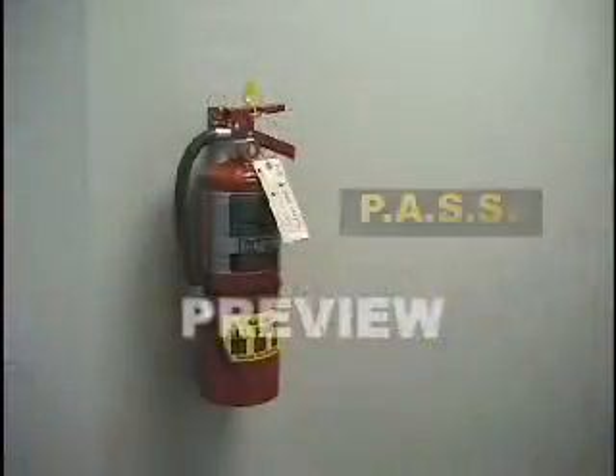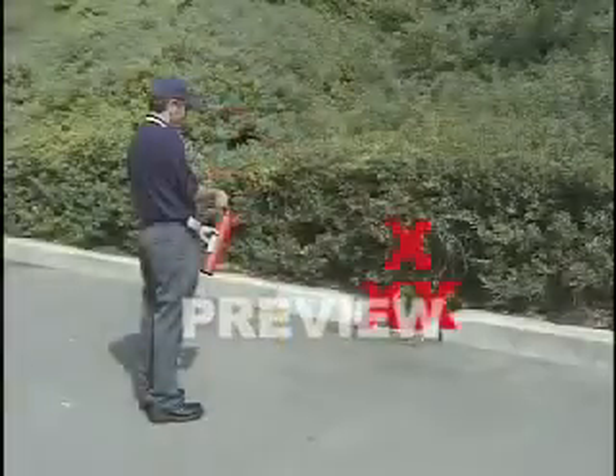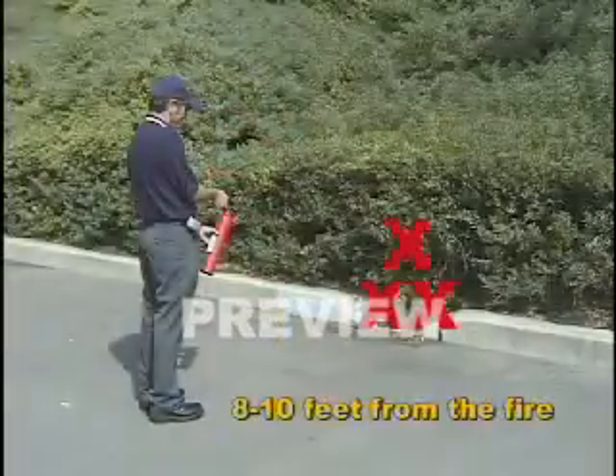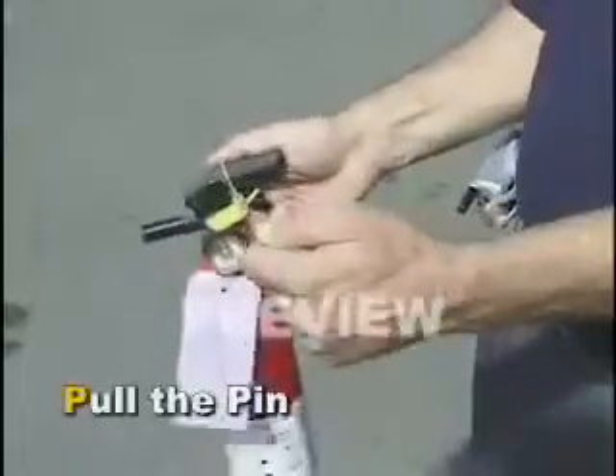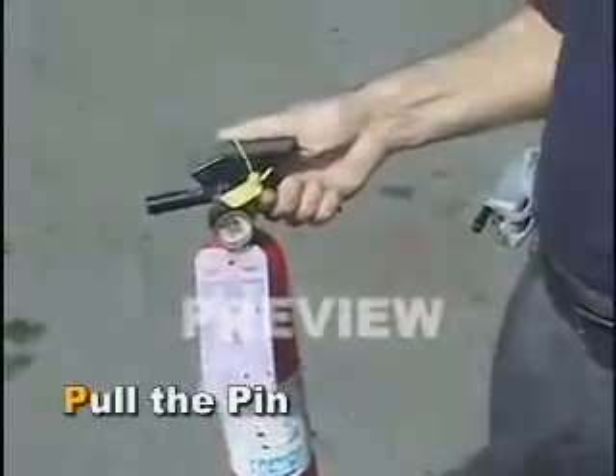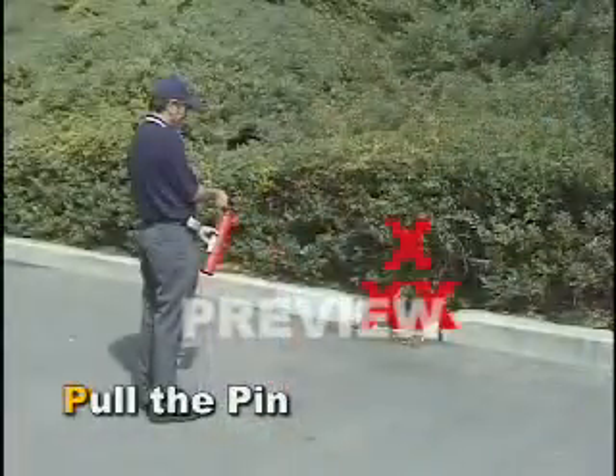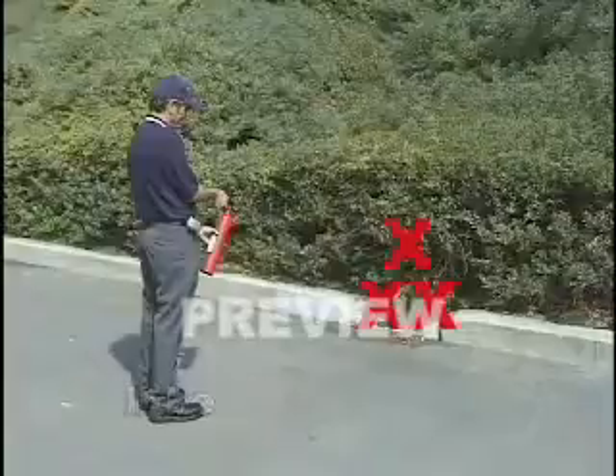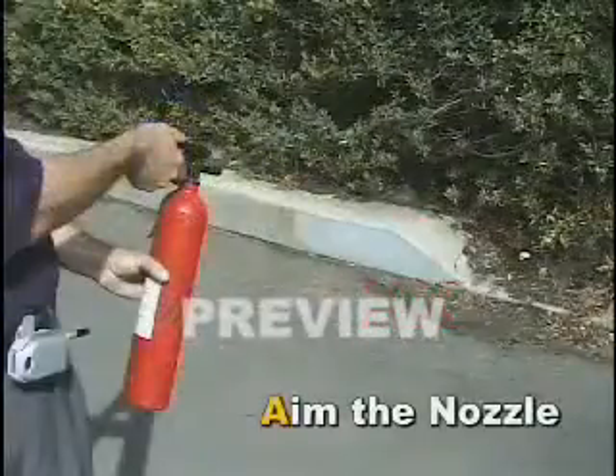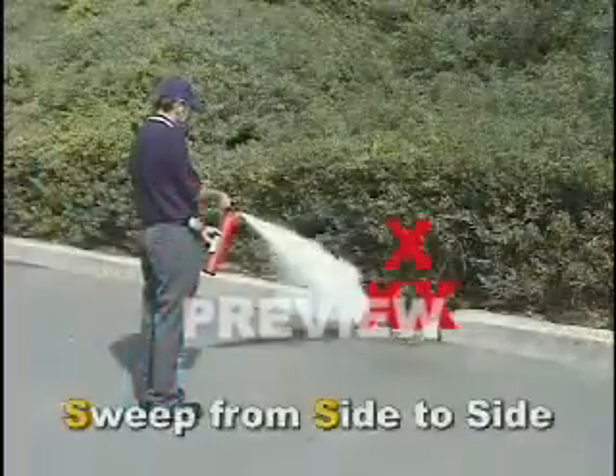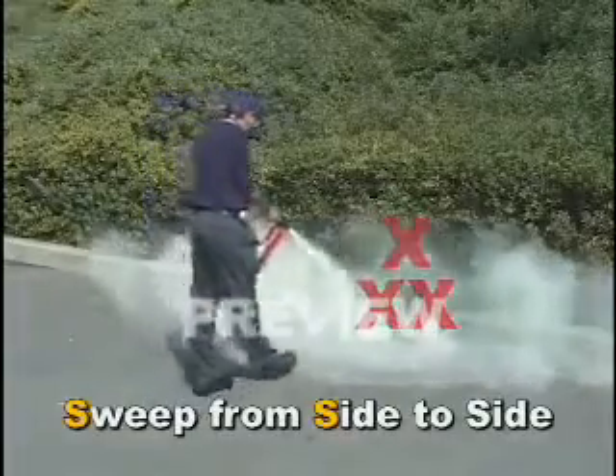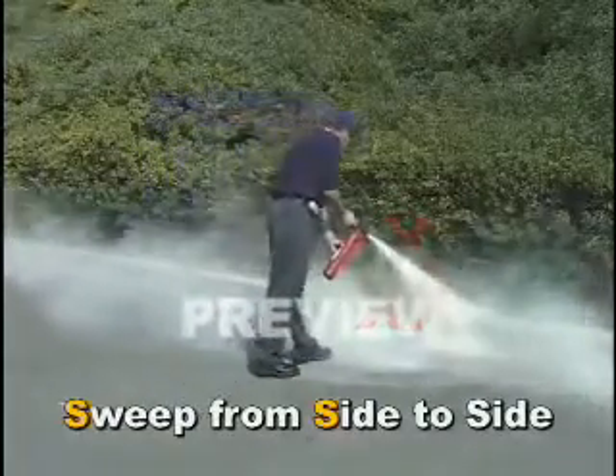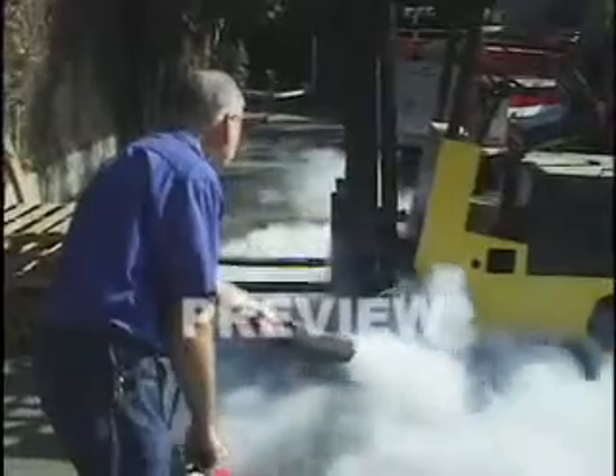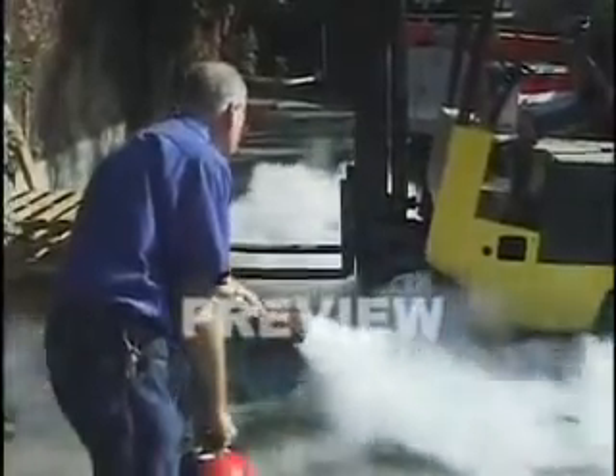When using a typical extinguisher, follow the PASS method. Hold the extinguisher upright and stand back 8 or 10 feet and pull the pin. If you stand too close, the pressure from the extinguisher can actually spread the fire. Aim at the base of the fire. Squeeze the handle. Sweep at the base from side to side. If you aim high at the flames, you won't put out the fire.